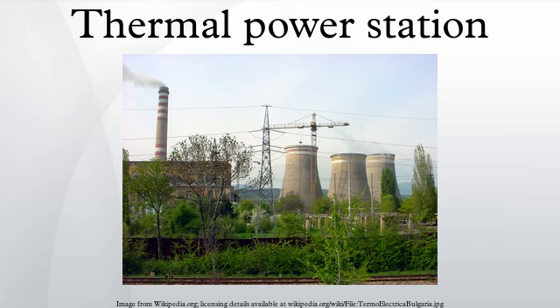Generator high-voltage system. The generator voltage for modern utility-connected generators ranges from 11 kV in smaller units to 22 kV in larger units. The generator high-voltage leads are normally large aluminium channels because of their high current as compared to the cables used in smaller machines. They are enclosed in well-grounded aluminium bus ducts and are supported on suitable insulators. The generator high-voltage leads are connected to step-up transformers for connecting to a high-voltage electrical substation for further transmission by the local power grid. The necessary protection and metering devices are included for the high-voltage leads. Thus, the steam turbine generator and the transformer form one unit.